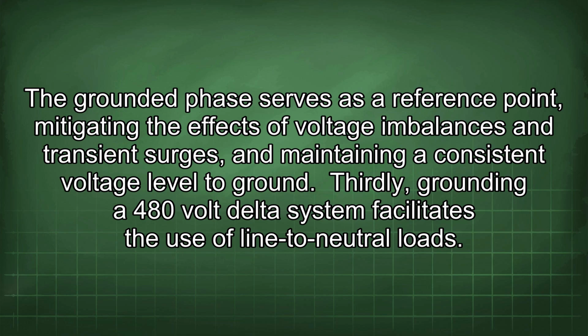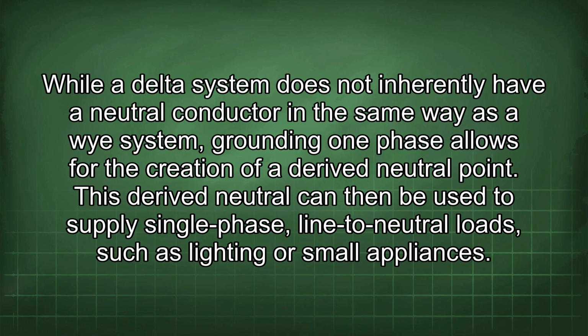Thirdly, grounding a 480-volt delta system facilitates the use of line-to-neutral loads. While a delta system does not inherently have a neutral conductor in the same way as a Y system, grounding one phase allows for the creation of a derived neutral point. This derived neutral can then be used to supply single-phase, line-to-neutral loads, such as lighting or small appliances.